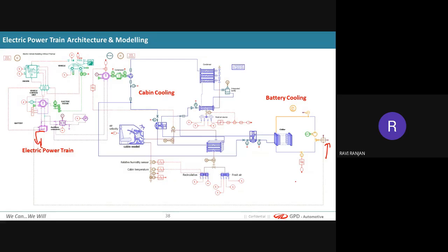Our aim is to keep the battery between 15 to 35 degrees Celsius. That's why the liquid cooling channel is deployed, supported by the chiller unit. Whenever temperature shoots above 35 degrees Celsius, the chiller gets triggered on, and when it comes down below 15 or around 30 degrees, the chiller gets switched off.